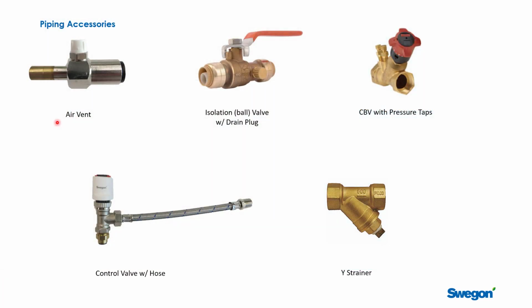Some things about accessories that you often see associated with chill beams. So an air vent, not a bad idea. So you can have a unit in here that would allow you to bleed the air out. It's always a good idea to have some form of isolation valve. Nice thing to do is to get one with a drain plug in it.